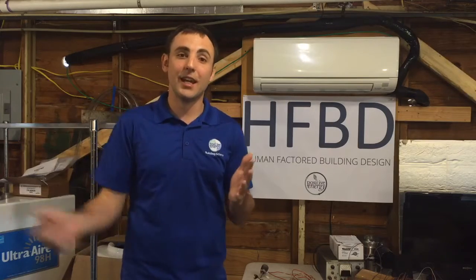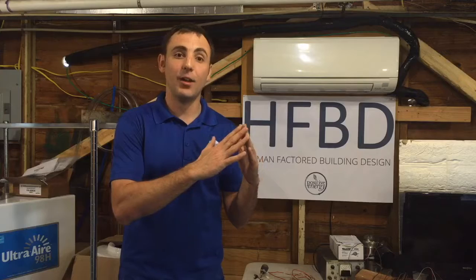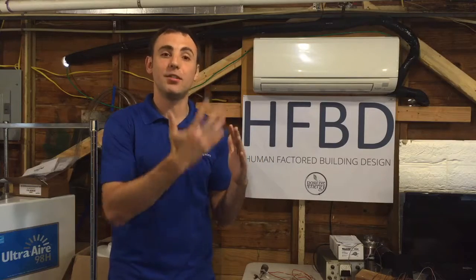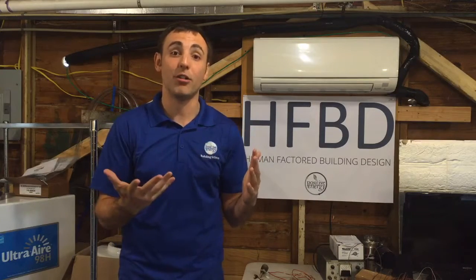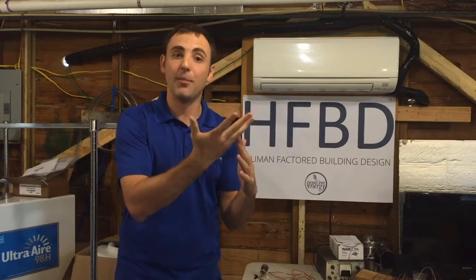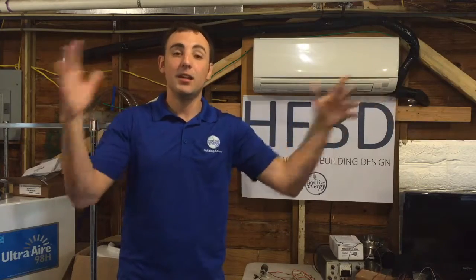But the problems with it, not just from an air quality perspective, but also from an efficiency and airflow perspective, is that air that's getting drawn in is going to be a lot warmer than the air that's already conditioned. So your coil in your house is designed to decrease the temperature of the air by about 20 degrees. Your house is typically about 75 degrees, and it's going to then cool the air by about 20 degrees, give you 55 degree air coming out of your vents to then cool the house and start the process all over again.